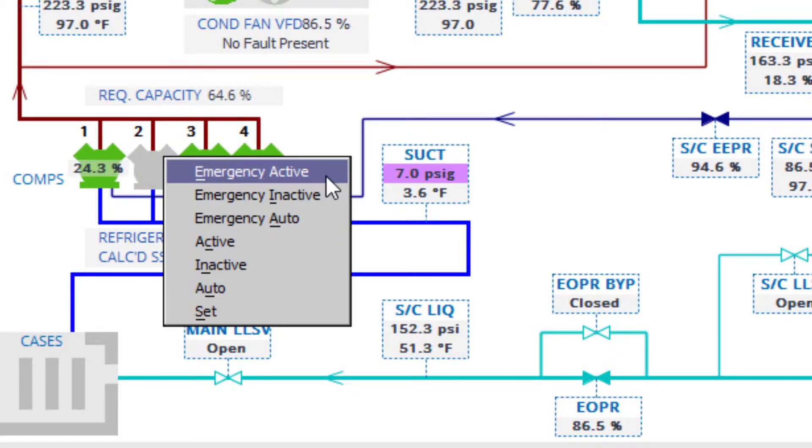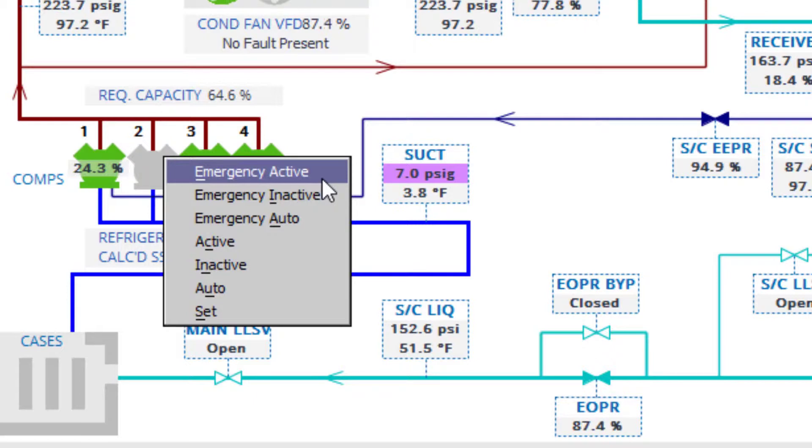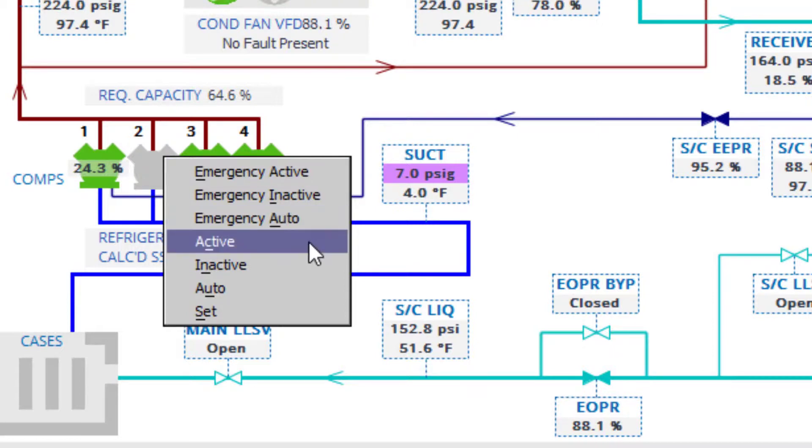Forcing an emergency override would disregard any and all of these failsafe features and will immediately force a change at the control point. It is always recommended and safer to use the regular override option.